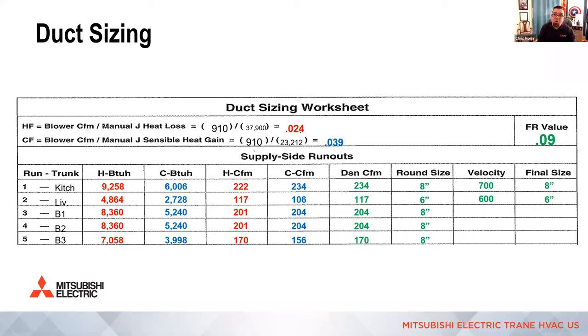If you're not, if you're using more of a worksheet style, it does this calculation for you. But you have to make sure you enter in the right fittings you're using, the right static pressure you're starting with, the right volume of air you're starting with. Otherwise, this uses default values, maybe off of an AHRI certificate or something. So you have to look up the manufacturer's specs to enter into the design software to get the right output. It's just a calculator. If you put the wrong numbers in, you're going to get the wrong numbers out, right? So we do the same all the way down. You can see that last run, 170 CFM and an 8-inch was way too low static. So we had to go to a 7-inch to get the velocity back up.